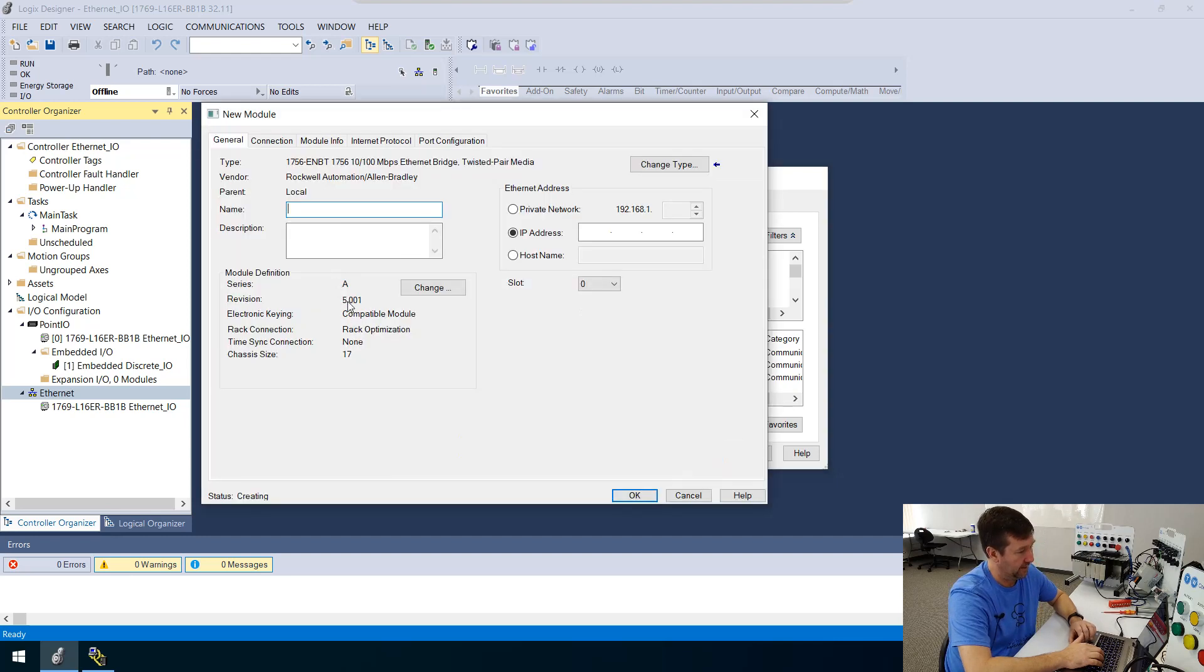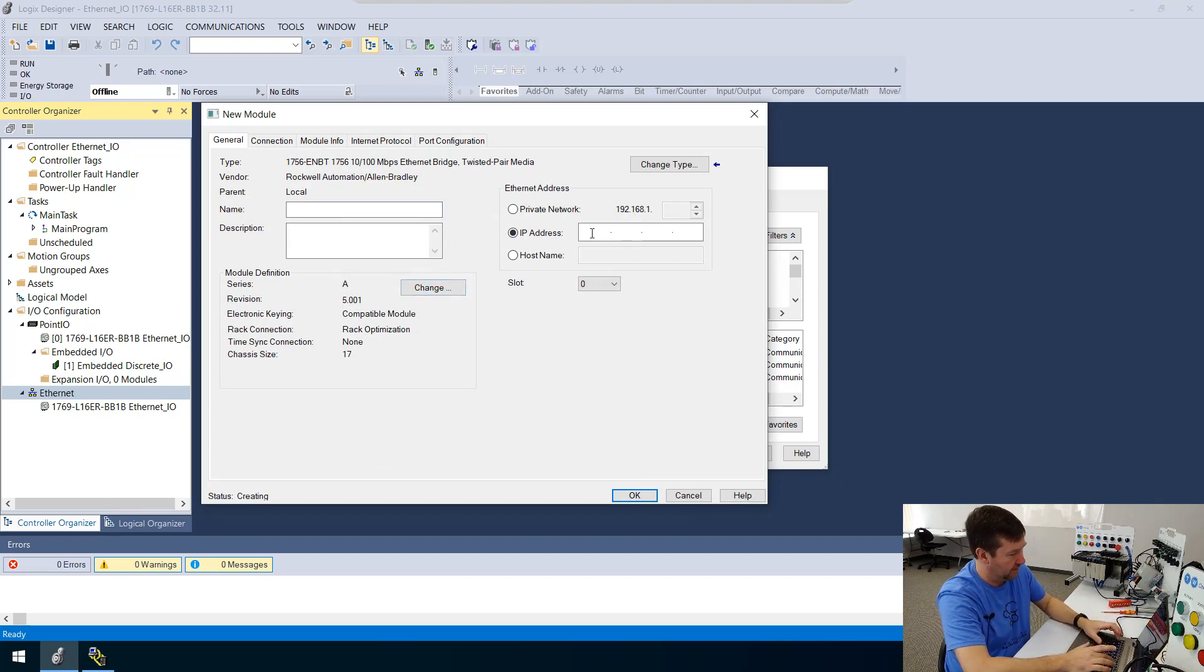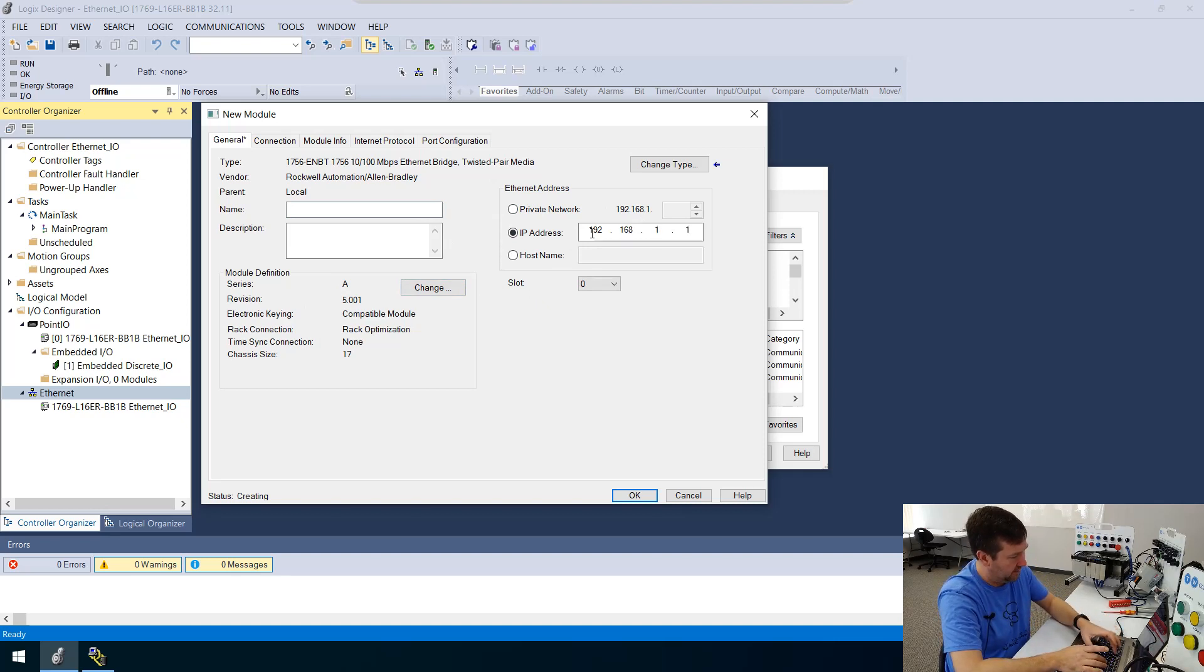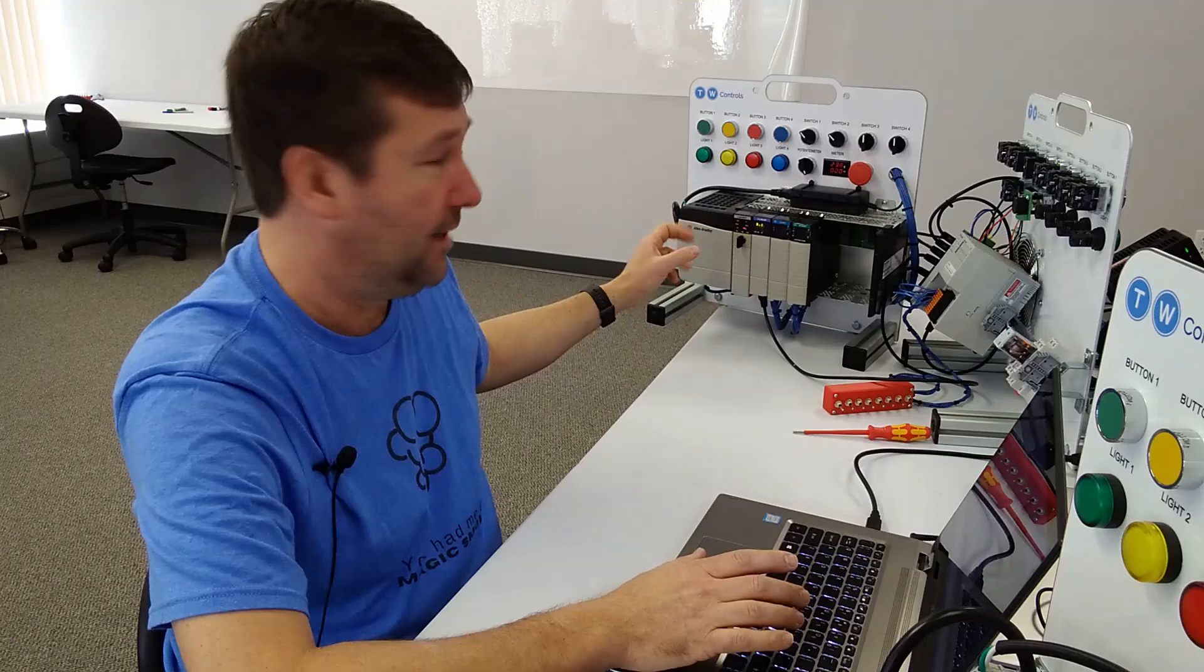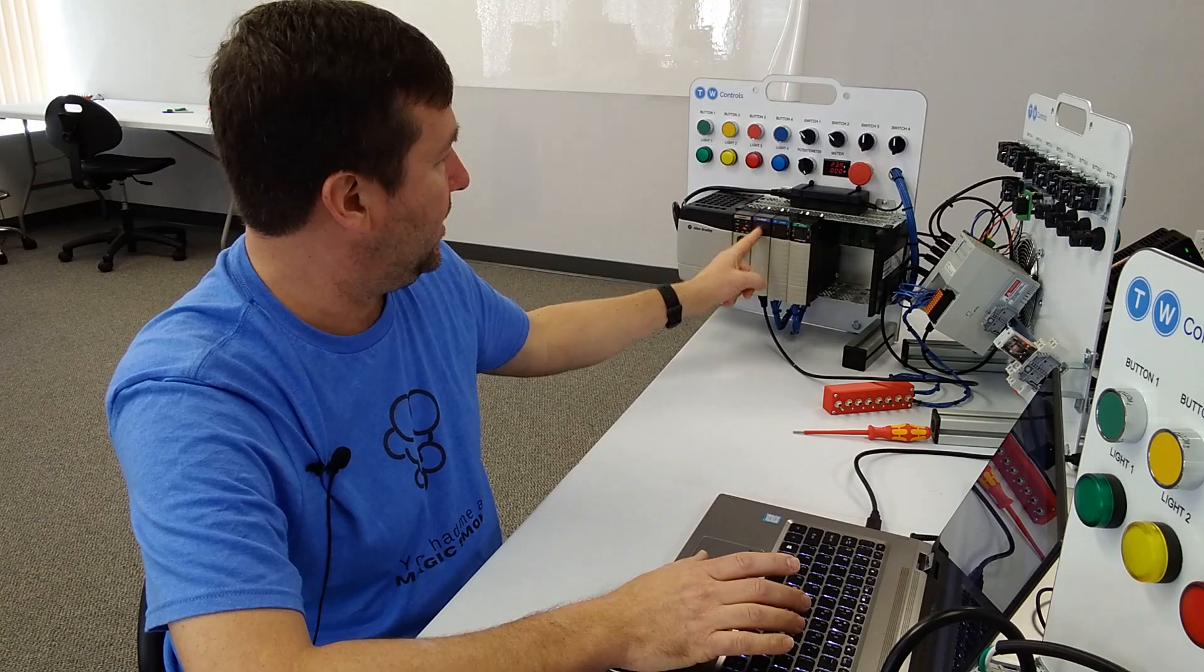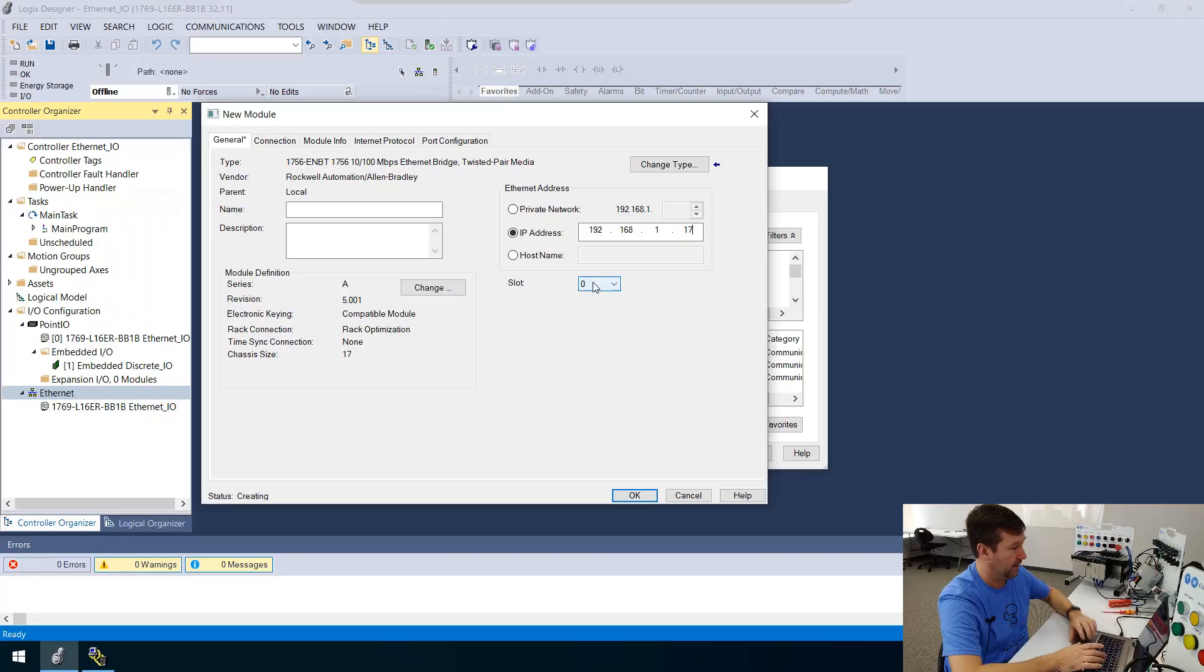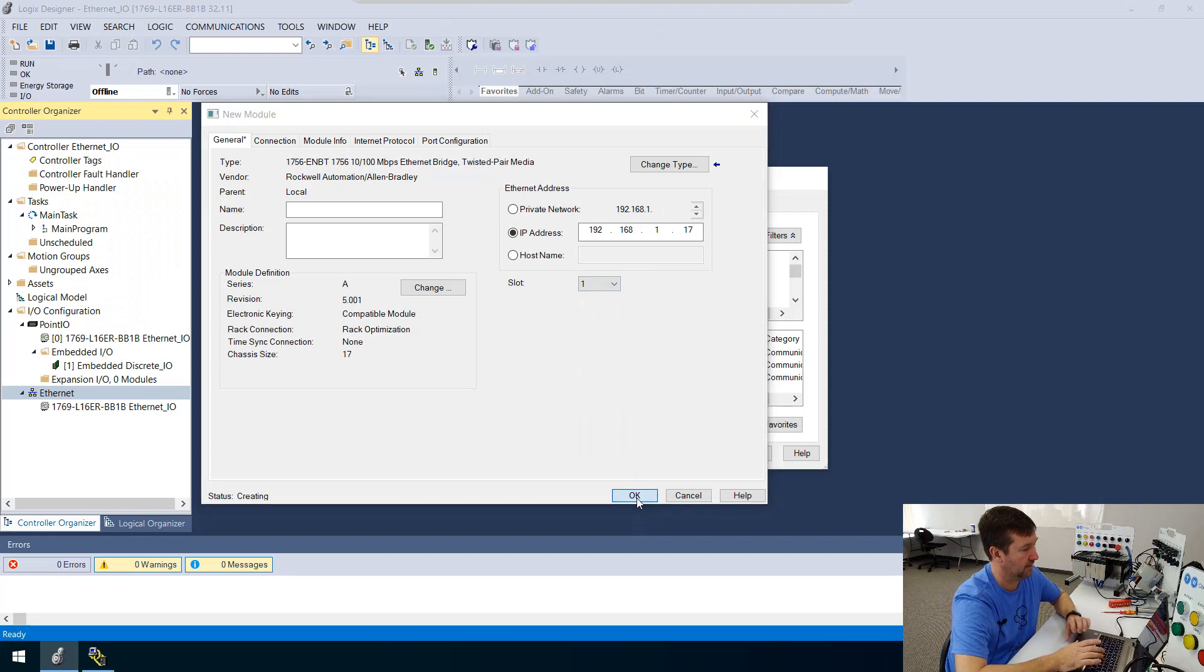And revision there is 5.001. We could change it if we had an older or newer revision. And our IP address is going to be 192 168 117. And it says here, what slot is it in? And this is important. So we are going to be in slot one.